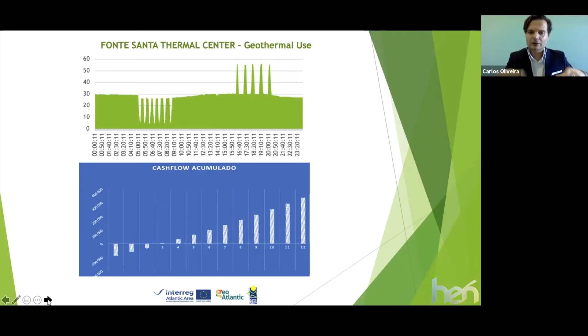The savings will be 83%. It's not normal, the investment in energy efficiency in Portugal will have such a big impact. But when we do the energy audit of the building, we will see that if we take the consumption of the chiller and change it to a heat pump, the coefficient of performance will be stable, about 4. We will have very high savings for this building, so our expectations are very high for this intervention, and we will see closely how this building behaves.